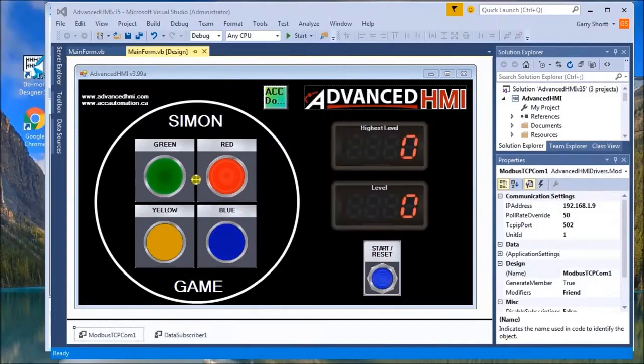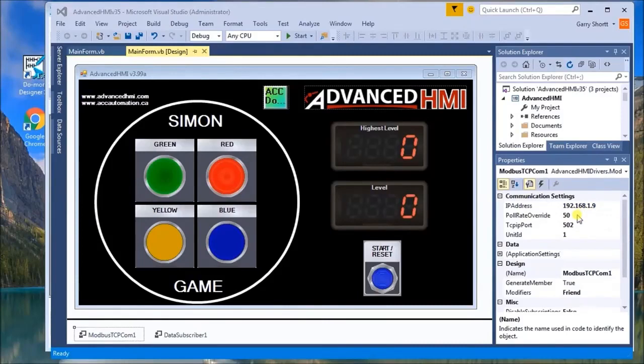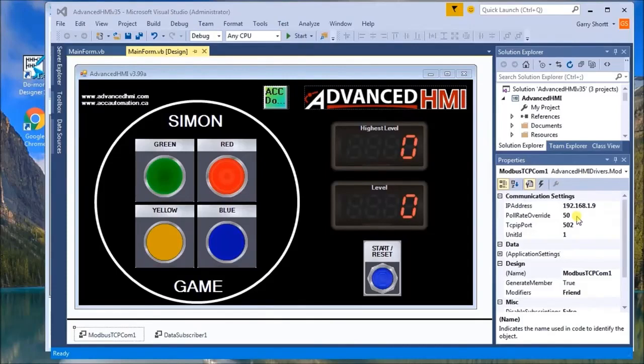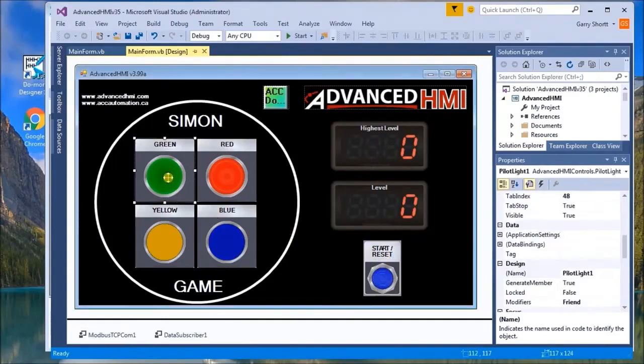The first thing to do is to program this all in your HMI. If we look at our Modbus settings here, our address, then our polling rate—this is the polling rate to communicate. That's been reduced so that we can account for some of the sounds that we're going to have in our HMI, and then we have our port address.